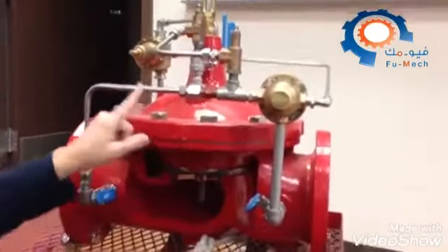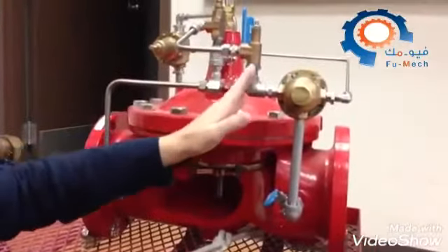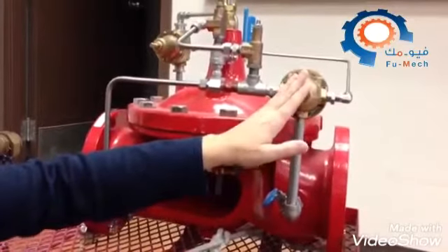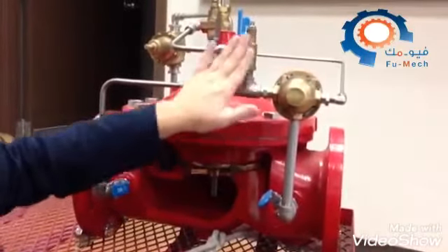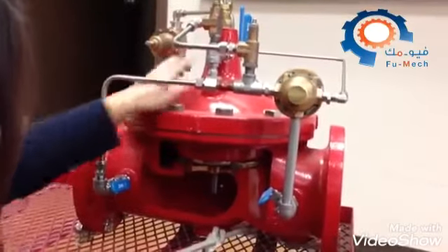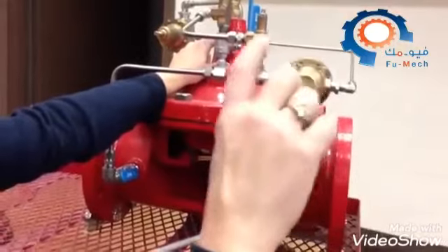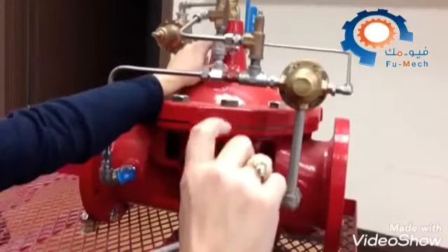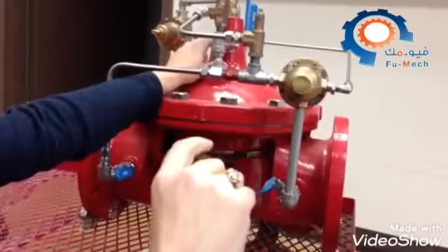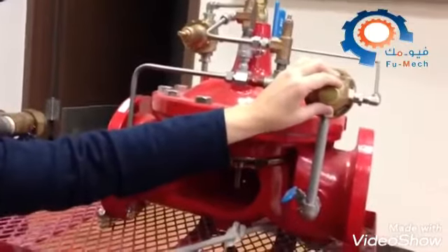When it closes, that 0.1 liters per minute is then forced, or a fraction of it. It generally doesn't close all the way. More of it will be forced onto the top of the valve, which pushes the water in here, which forces this stem to travel down and close, which will start to close the valve. Now, this process is very minute. We're not talking like open, close. So this valve is going to be partially open almost all the time.